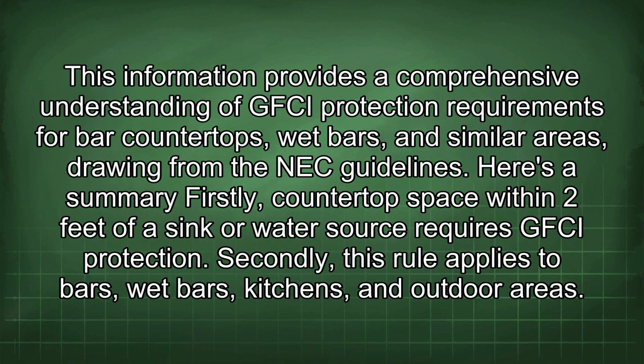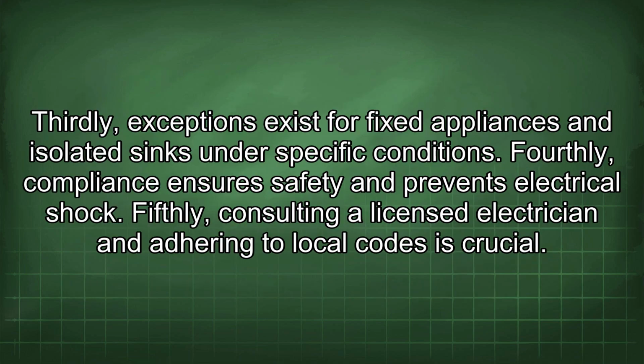This information provides a comprehensive understanding of GFCI protection requirements for bar countertops, wet bars, and similar areas, drawing from the NEC guidelines. Here's a summary. Firstly, countertop space within 2 feet of a sink or water source requires GFCI protection. Secondly, this rule applies to bars, wet bars, kitchens, and outdoor areas. Thirdly, exceptions exist for fixed appliances and isolated sinks under specific conditions. Fourthly, compliance ensures safety and prevents electrical shock. Fifthly, consulting a licensed electrician and adhering to local codes is crucial.